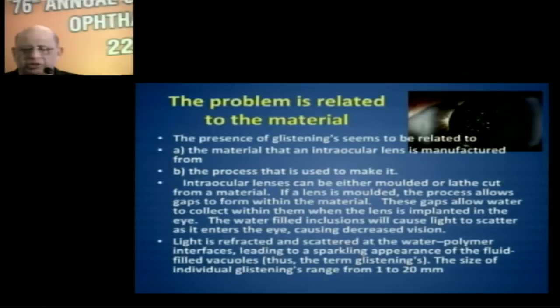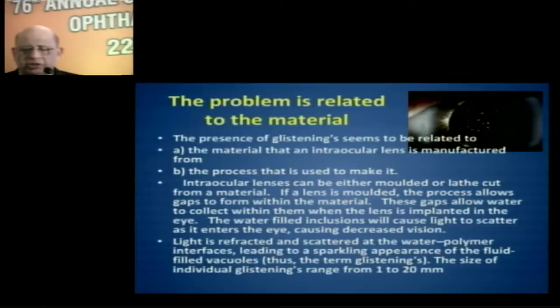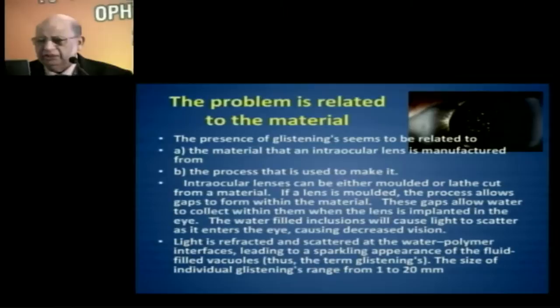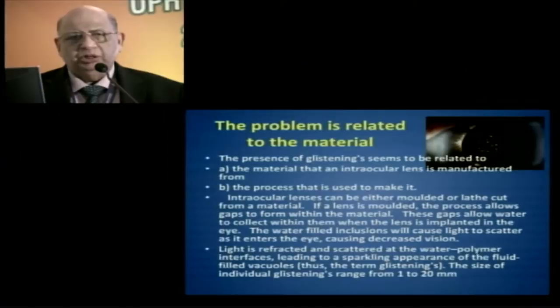The problem is essentially related to the material from which the lens is manufactured and the process by which it is made. Intraocular lenses can either be molded or lathe cut. If a lens is molded, the process allows gaps to form within the material. These gaps allow water to collect, and the water-filled inclusions cause light to scatter at the water-polymer interface, leading to a sparkling appearance — hence the term glistening.